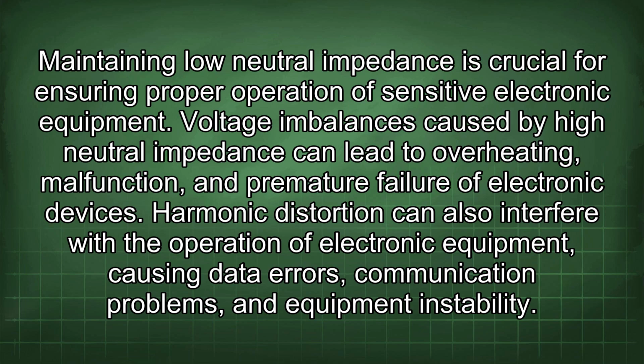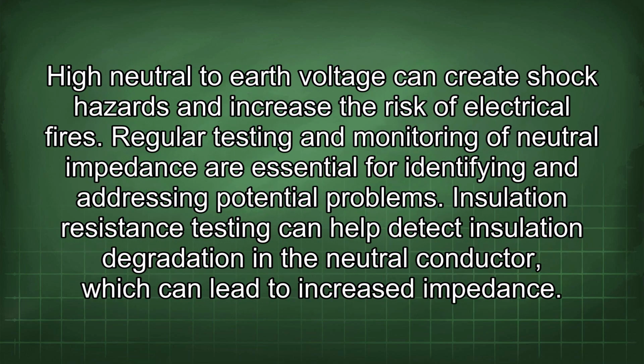Harmonic distortion can also interfere with the operation of electronic equipment, causing data errors, communication problems, and equipment instability. High neutral-to-earth voltage can create shock hazards and increase the risk of electrical fires. Regular testing and monitoring of neutral impedance are essential for identifying and addressing potential problems. Insulation resistance testing can help detect insulation degradation in the neutral conductor, which can lead to increased impedance.